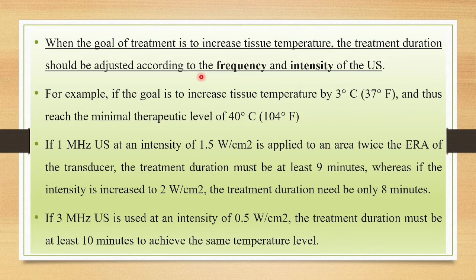And if 3 megahertz ultrasound is used at an intensity of 0.5 watts per centimeter square, the treatment duration should be at least 10 minutes to achieve the same temperature level. So it all depends upon the frequency and intensity of the ultrasound.